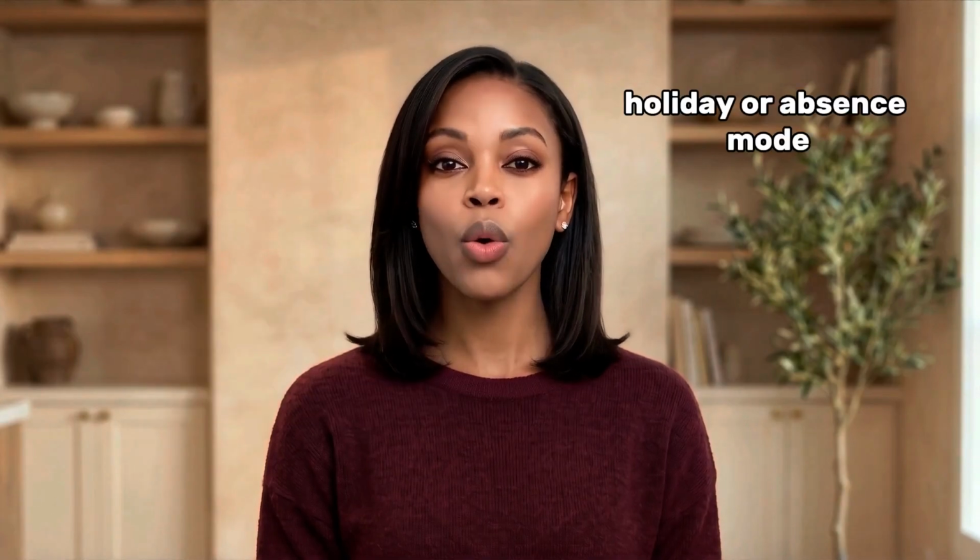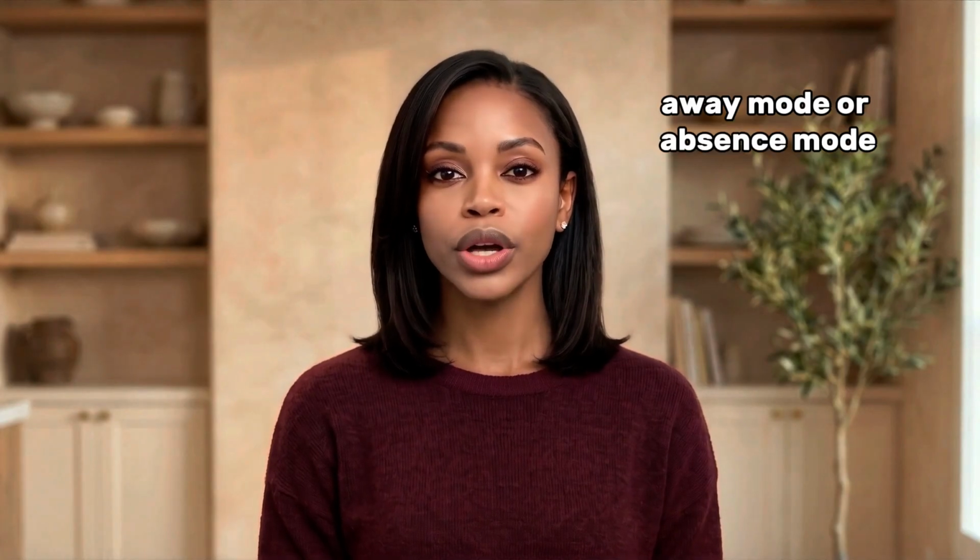Setting 3, holiday or absence mode. Now imagine you're leaving home for 10 days in January. You don't need the house maintained exactly as though you're sitting in the living room, but switching the entire system off without understanding what that does isn't necessarily the answer either. This is why many controllers provide something called holiday mode, away mode, or absence mode. The name varies, and importantly, what the function does also varies, like reducing the normal space heating operation. It may allow you to enter a return date or maintain frost protection functions. So, before you travel, find the function in your manufacturer's manual and establish exactly what it changes.